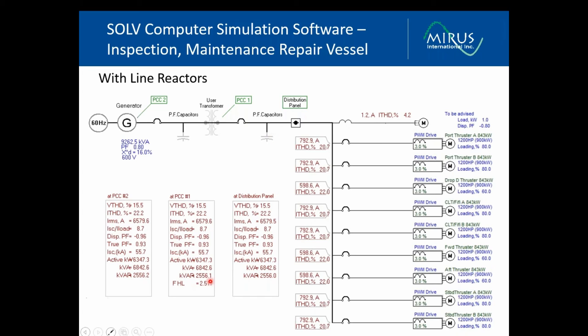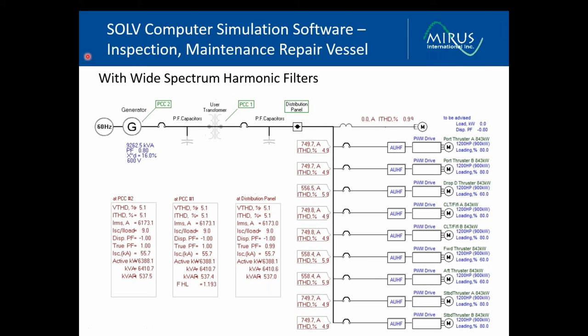We run the simulation, and it produces the voltage and current harmonics. There's a lot of other information that can be generated from this simulation, such as the waveform spectrums and reports. Here you can see that the voltage distortion was over 15%, with current distortion around 22%, so well above any of the marine harmonic standards.